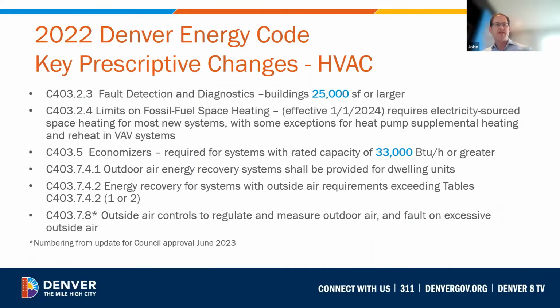There's a section that was previously specified here as 403.7.1 and has now been relocated as C403.7.8 for outside air controls that apply to energy recovery ventilation devices, dedicated outside air systems or DOAS, and makeup air systems that report when the systems provide excess outside air. For systems with an outside air flow rate above 4,000 CFM, direct airflow measurement is required. So this is essentially a requirement as a checkpoint to ensure that excess outside air isn't delivered to the space, which would increase the cooling and heating loads when it is not needed.